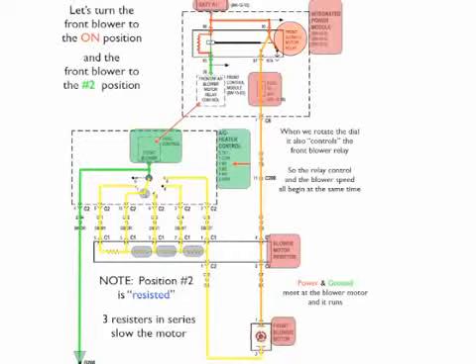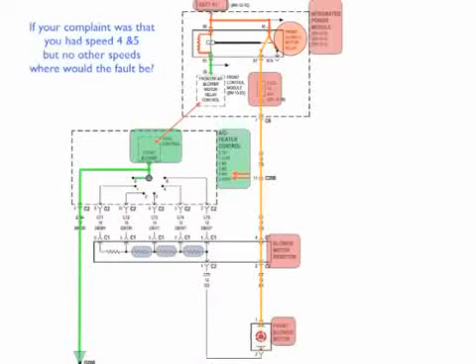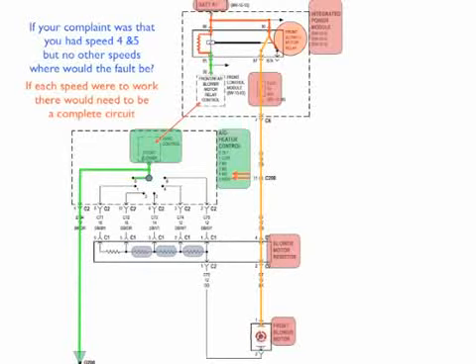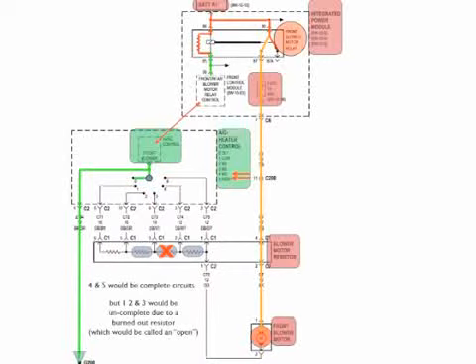Now number 2 is the only one that has a direct path to the motor, but it has 3 resistors in it. So when you're in this position, the motor is going to run with 3 resistors in it. Now if you had a complaint, and that was that speed 4 and 5 worked, but no other speeds were working, where would the fault be? As you look at this, if each speed were to work like they should, each speed as we rotated that dial should have a completed circuit, a direct path from the ground to the motor. But if we had one of these resistors that was blown out or burned out, then in this case, if this resistor was burned out, 4 and 5 would be complete circuits, but 1, 2, and 3 would be incomplete because of the burned out resistor. That's where our open would be.